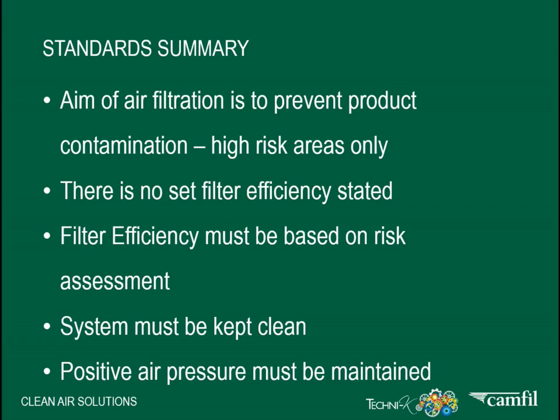So to summarize, the standards say that we have to have filtration as a minimum for high-risk areas, but unfortunately, they don't tell us what exact filter we need to use to do this. They just say that we need to create a risk assessment to work out what the filter size should be, and we need to make sure that we keep the system clean. And when we say clean, we need to prove that it's clean. So that would require monitoring of air plates, for example. And all the while, we've got to maintain positive air pressure.